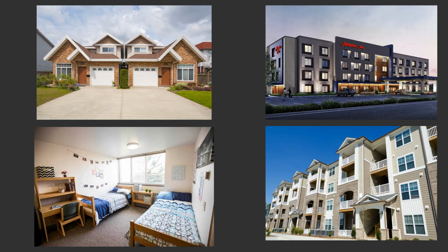Smaller ones may be type 5 stick build again. This one is looking a little big for that. However, we can tell clearly that's not type 1 construction because it has the wooden balconies on the outside. You can see the undersides of the balconies, the wood supports, the wood railings. You're not going to see that on a type 1 building because it's a combustible object, combustible materials. So that one I'd be fairly confident locking into the type 2 construction category.